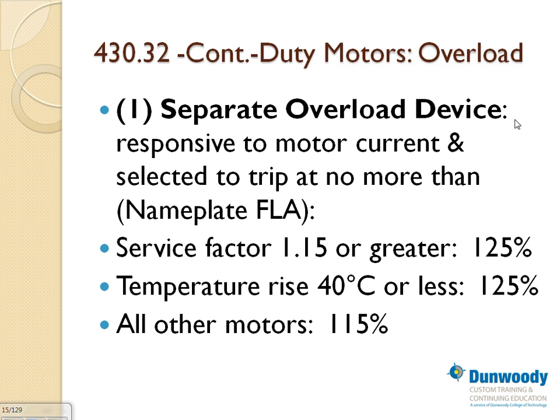It was expensive. It's not like the light. Why don't we have an overload protection at this fixture here? We don't have an overload protection now, and we depend on the circuit breaker to protect that, right? Yeah? Disconnect, but does it come with overload? You have to have a disconnect with it by the new code, but you don't have to have a tiny little overload. You can if you want to. Fuse each and every one of them? Yeah. Oh, okay. So it's special, that's more protection, but you don't need it by code.